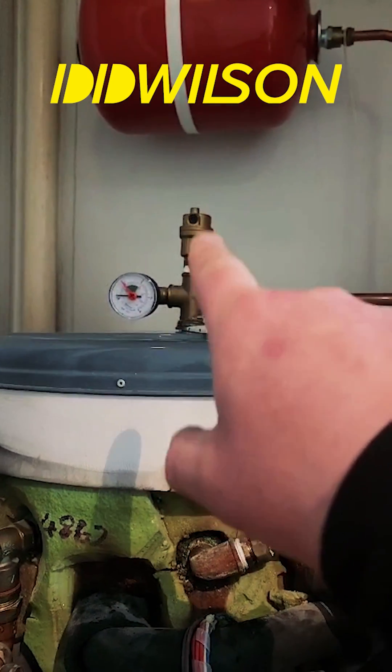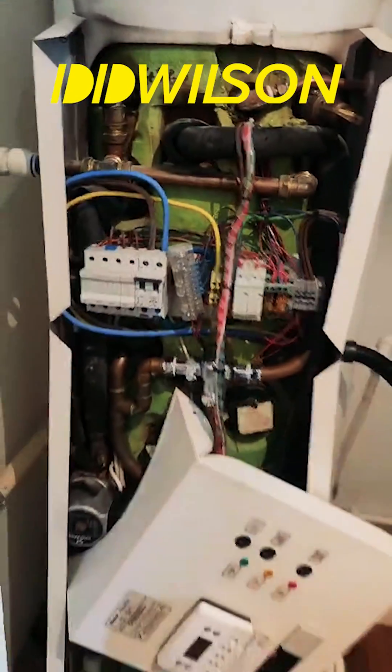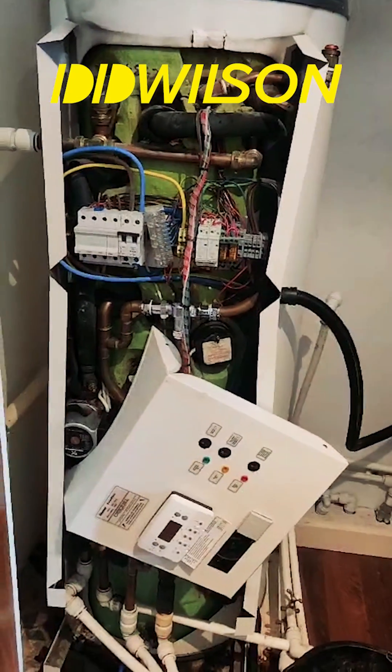It was also frothing and steaming out the auto air vents. He also noticed that when this was shut over, somebody had wiped clean the scorch marks, which identify that this is not working correctly and is unsafe.